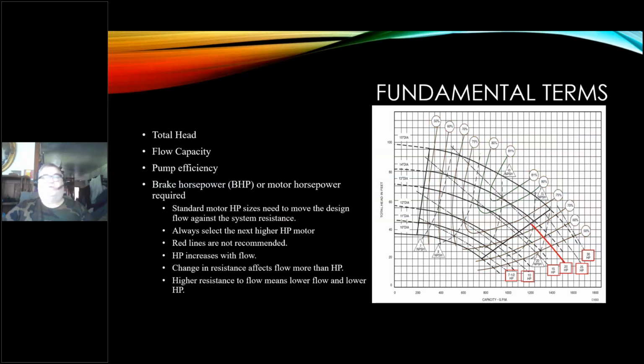Horsepower. This is where energy management comes into play. So I've outlined each one of the horsepowers, and if you select a pump, again, the limits are coming into play. They do not recommend that you use this pump outside these lines. Those dotted sections of the curves are in the bad zone. So if I pull up the first one, everything below that line to the left, curves will work on that 20 horsepower line. The next line down is a 15 horsepower, and these are the standard motor sizes. The next line down goes to 10 horsepower, and then the next down to 7.5. So if you choose your flow and resistance, you have to select a motor larger than where you land on your pump curve in order to move that water. Otherwise, you will have a problem. You will not be able to move it. It will overheat, overload the motor, and you cannot move it.